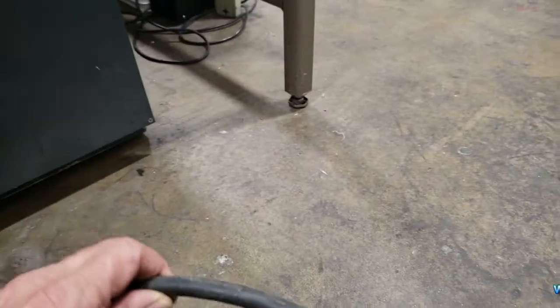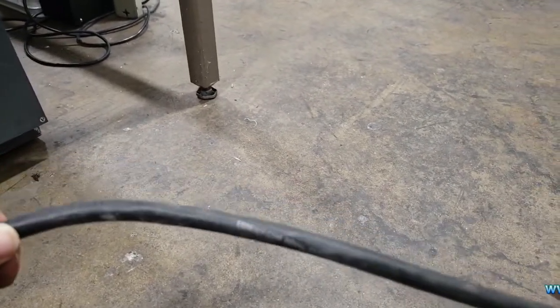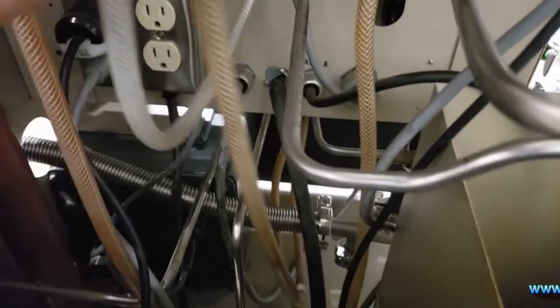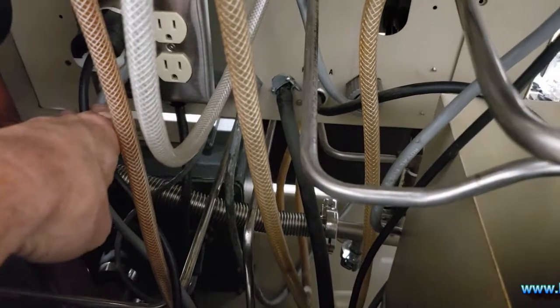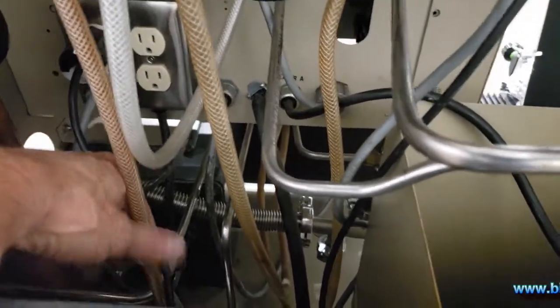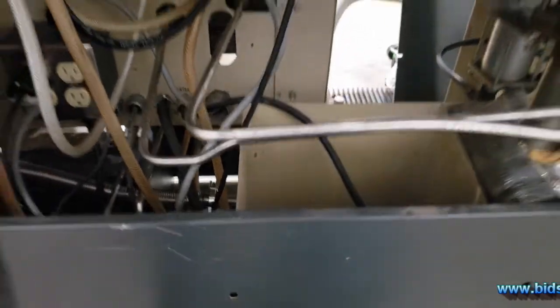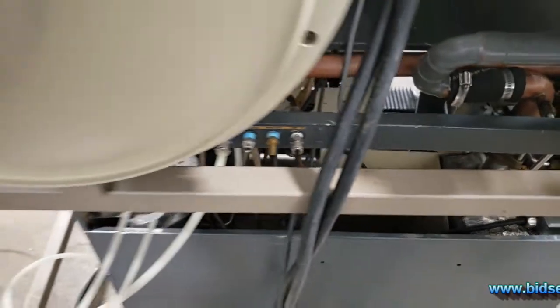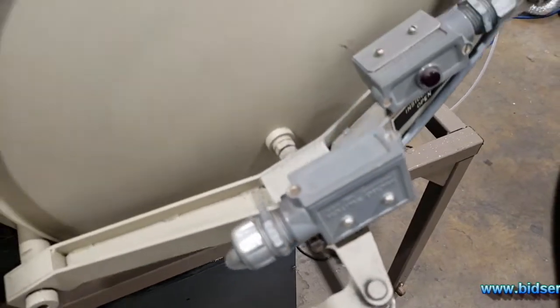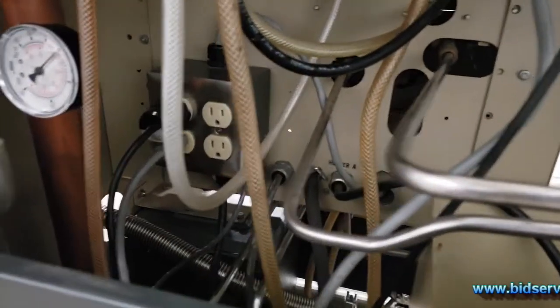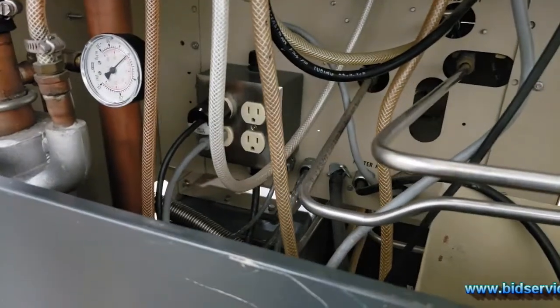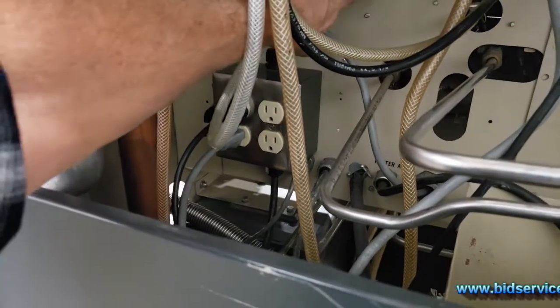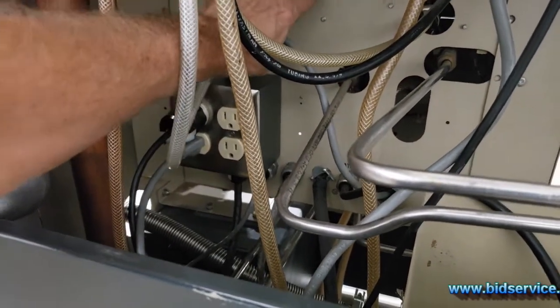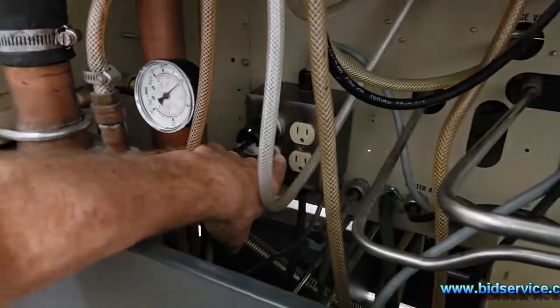It also has a 110 power supply in there, a 110 power cord coming out of there, 20 amps on that. There's an outlet down here where you can plug in your lights, and an outlet up on the top. And then I also have 110 for your indicators here, for your lights to indicate whether the doors are open or closed. You need 110 volts for that too. Also, the 110 is run independently for your circulator, the 110 circulator. There is an outlet out here for the pump. If you do have a 230 volt pump or 208 volt pump, you can plug it in here where it says vacuum pump. If it's 110 volts, you can go ahead and plug it in down here in the outlet.